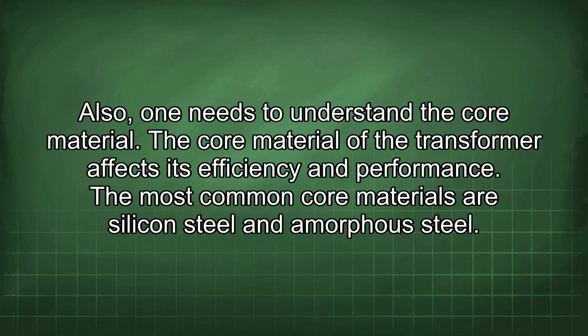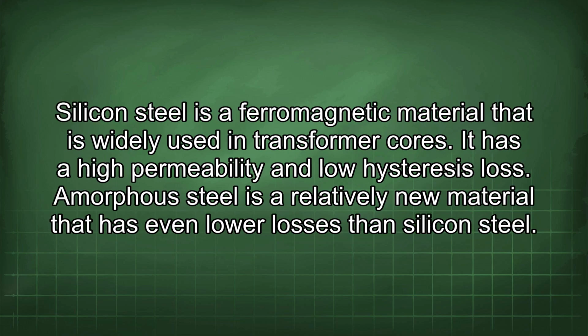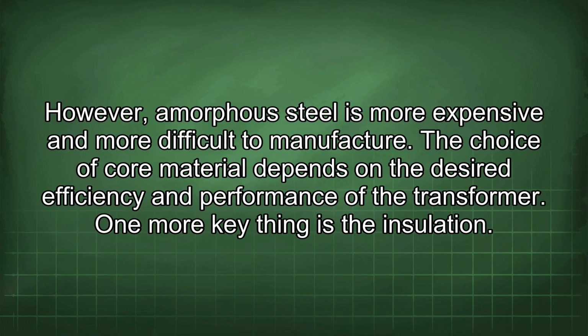Also, one needs to understand the core material. The core material of the transformer affects its efficiency and performance. The most common core materials are silicon steel and amorphous steel. Silicon steel is a ferromagnetic material that is widely used in transformer cores. It has a high permeability and low hysteresis loss. Amorphous steel is a relatively new material that has even lower losses than silicon steel. However, amorphous steel is more expensive and more difficult to manufacture. The choice of core material depends on the desired efficiency and performance of the transformer.